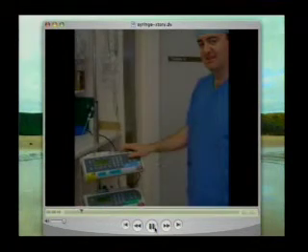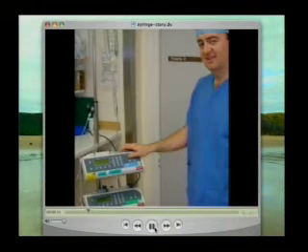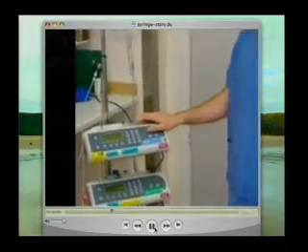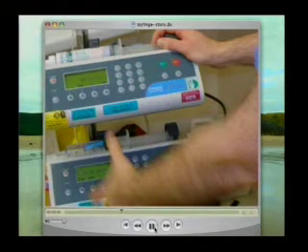Here we're outside Operating Theatre 2 in the Morriston Hospital. This is Mike the anaesthetist, and in front of us, although you can't see them, there's a patient lying down, and we're just starting to enter his weight into the syringe pump. There's no weight on his patient notes. He looks big, so is he 60 kilograms or maybe 70 kilograms? Maybe we have a discussion with him. Maybe he's 75. Oops, the pump is showing 5 kilograms.